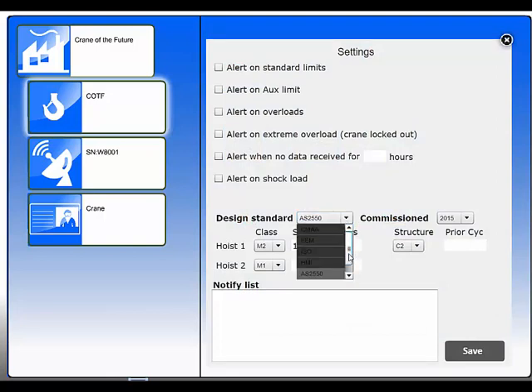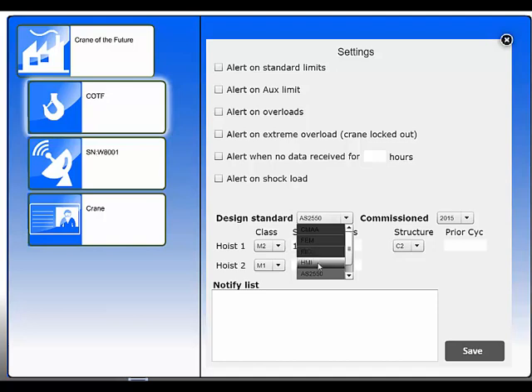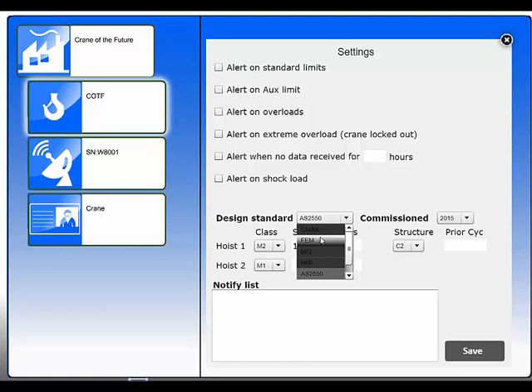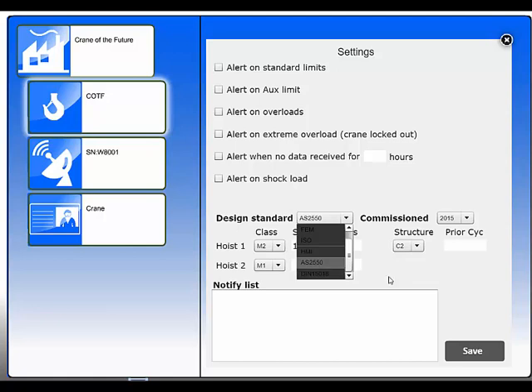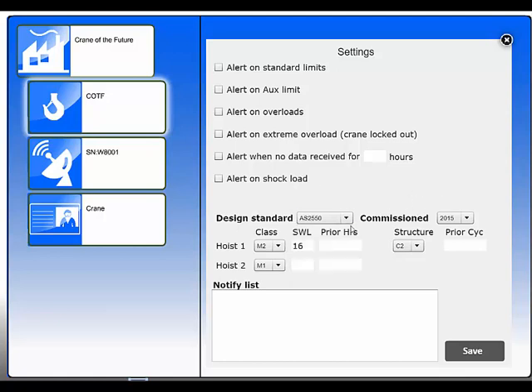Implementing some new standards, so you can assess the remaining life according to the AS2550, a couple of American standards, the ISO and FEM standards as well. And if you've got a different way of calculating remaining life, we can plug that in. Or if you want to change the way you calculate remaining life, we can make a change, and because we store all of the data, we can recalculate the remaining life from scratch.